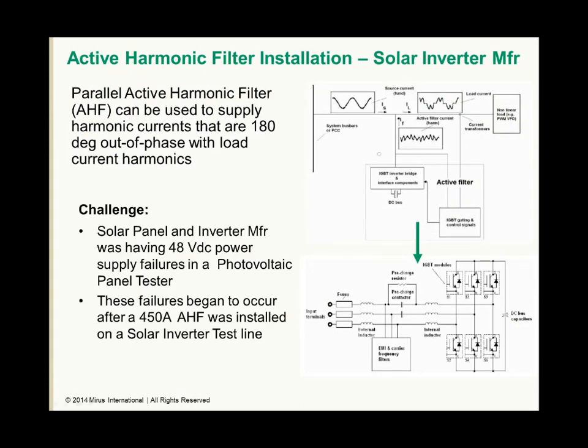The facility was now manufacturing solar panels and solar inverters, and a DC power supply in a photovoltaic tester was failing as soon as it was turned on. These failures began to occur after they installed a 450 amp parallel active harmonic filter, but they were not aware of this when they contacted me.